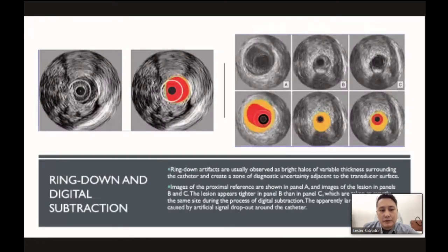Now, this is quite important. This is called the ring down artifact. It is usually observed as bright halos, like this one, of variable thickness surrounding the catheter. They are caused by acoustic oscillations in the transducer, which can result in high amplitude ultrasound signals that can obscure the area immediately adjacent to the catheter. So ring down artifacts create a zone of uncertainty.